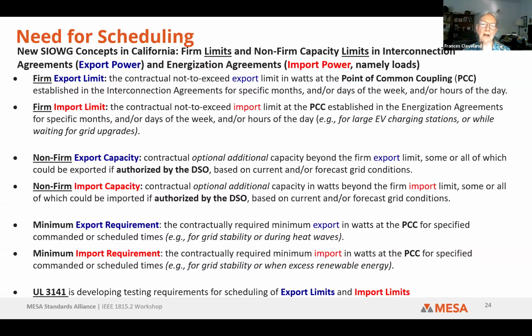So there's a concept of having firm limits, but firm limits have to be defined months, years ahead, and as everybody knows, that doesn't make it for very real. It might be very over restrictive to be limited by something you've designed a year ahead. So California is now looking at non-firm capacity limits that would be updated on a monthly, weekly, daily, even hourly basis so that they could be managed much more dynamically, much more flexibly. This is also being developed by UL 3141 for scheduling limits and import limits. So again, both the export and import.